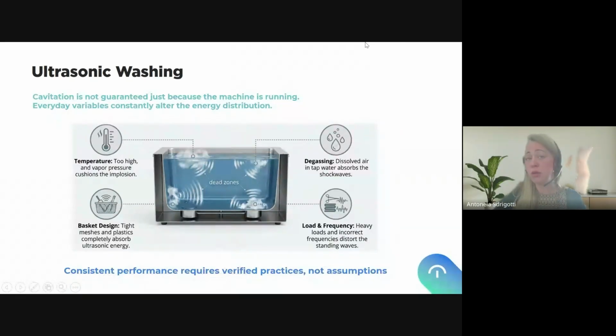Of course, the load and the frequency. Heavy loads or incorrect frequencies will distort the waves, the energy of cavitation. And basket design. We have to use the appropriate baskets, the ones that come with the machine or are recommended by the manufacturer in terms of materials. We have to make sure that we are not decreasing the cavitation energy due to using tight meshes or plastic baskets. So consistent performance requires verified practices, not assumptions.